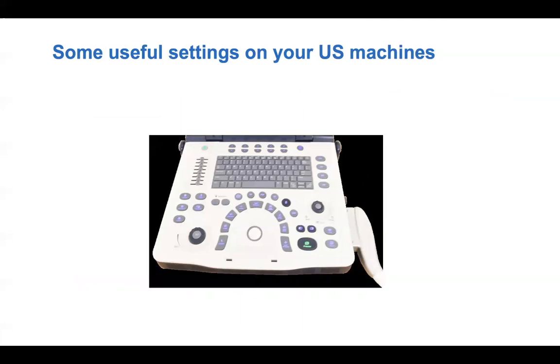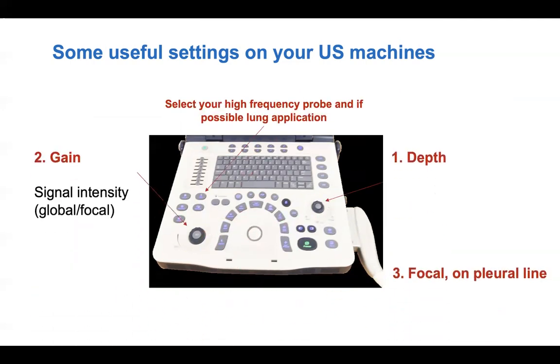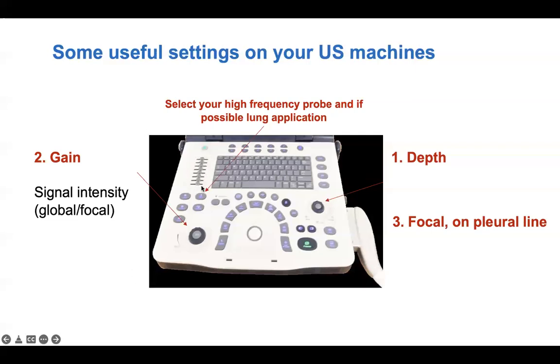As for any POCUS examination, the main settings to adjust before you start are, first, the depth, which should be set up at 3 to 4 centimeters. Second, the gain, which is the signal intensity, the brightness of your image. This can be adjusted globally or focally on the time gain compensation, time gain compensation being here. And the focal, which needs to be adjusted on the pleural line.